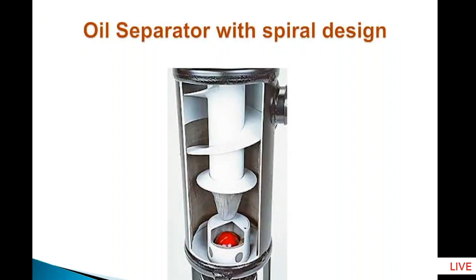The next design is a spiral oil separator. The oil and ammonia refrigerant move into a spiral, and in the process, the heavy, high-density oil falls down and the gas goes to the compressor. These are the various types.